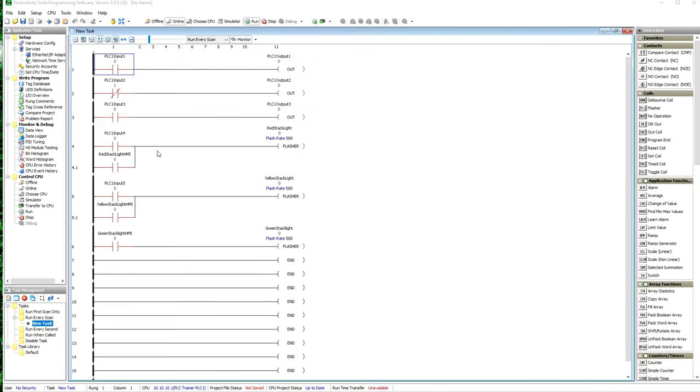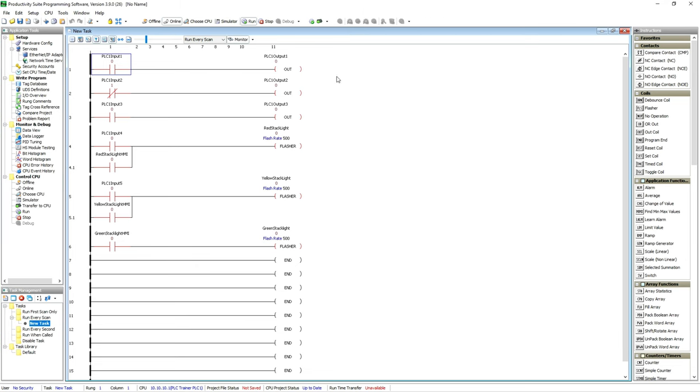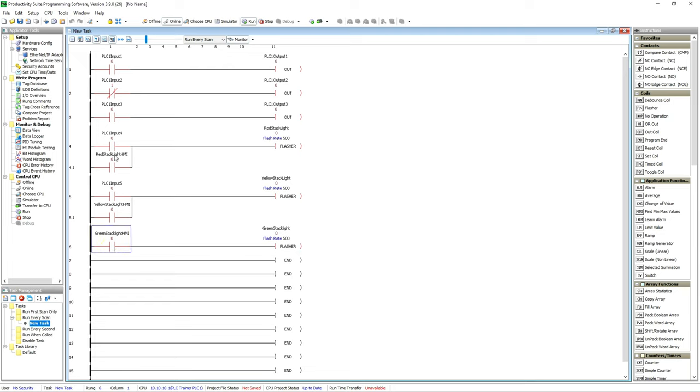The first thing we need is tags to work with from our PLC. We've got the Productivity Series software right here and I've written a little program—just tying some inputs to some outputs. In here I've added three specific tags: one for a red stack light, one for a yellow stack light, and one for a green stack light. Notice I put HMI at the end of those—that's because those are the tags we're going to use in the HMI.